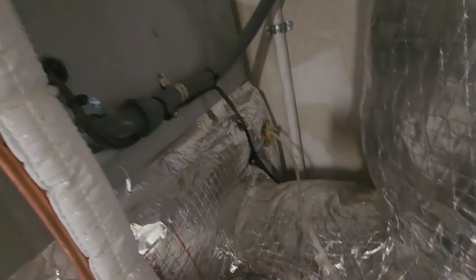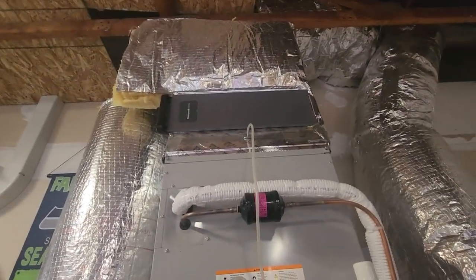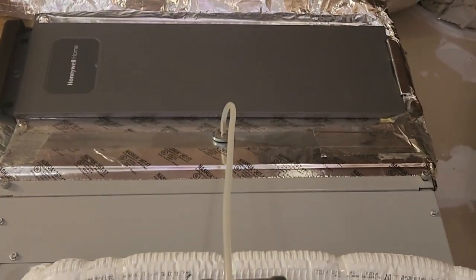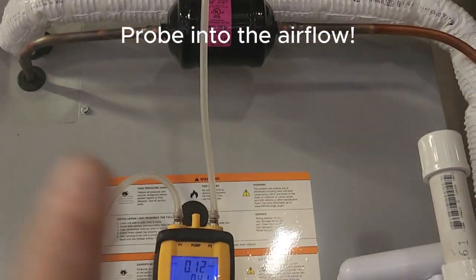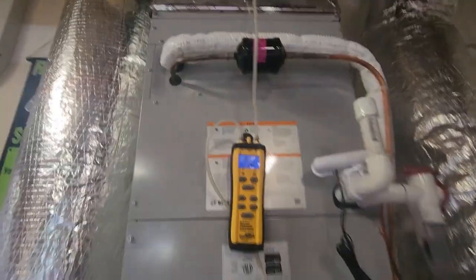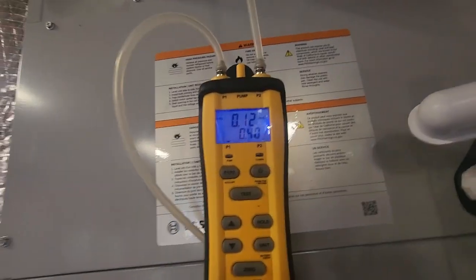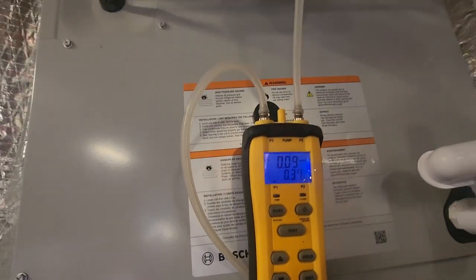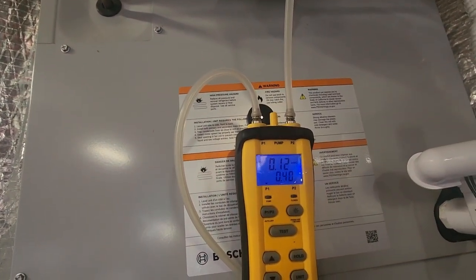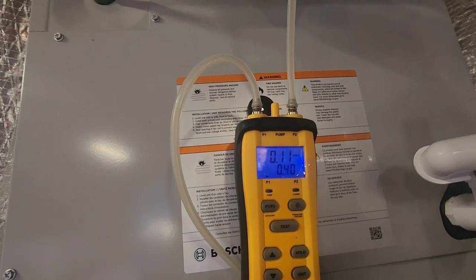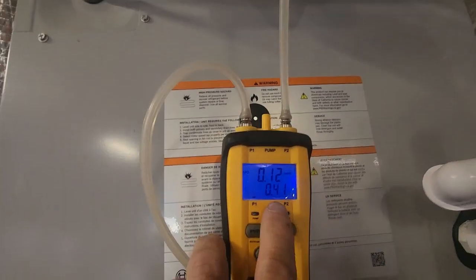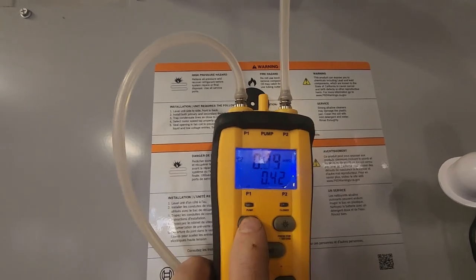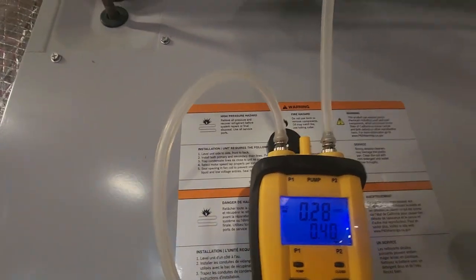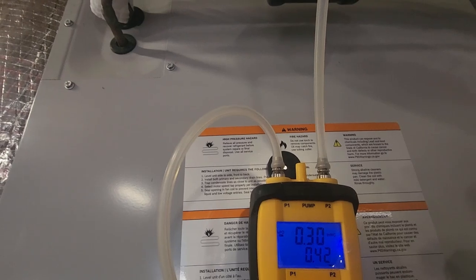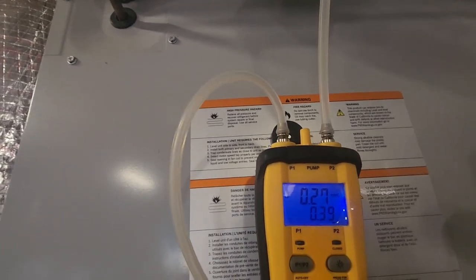Okay guys, we're all hooked up. You can see I've got my probe in my supply here, and up there, my probe in the return. Both are pointing, let's back that out, both are pointing that way. I've got pretty good static on my system with both wide open. We're bouncing around between 0.1 and 0.12, 0.09 on my supply. P2 is my return, the top number, 0.28. That's with the filter in place, and that's about what you hope to achieve on these systems.